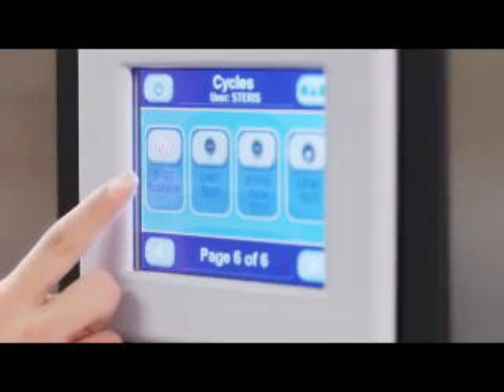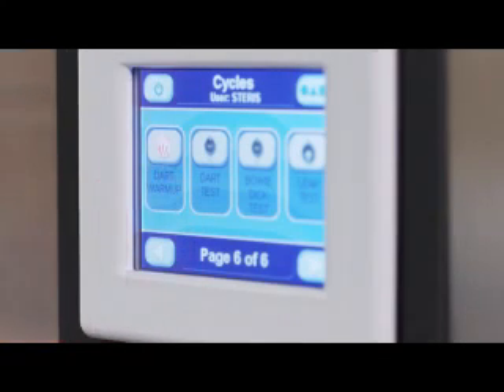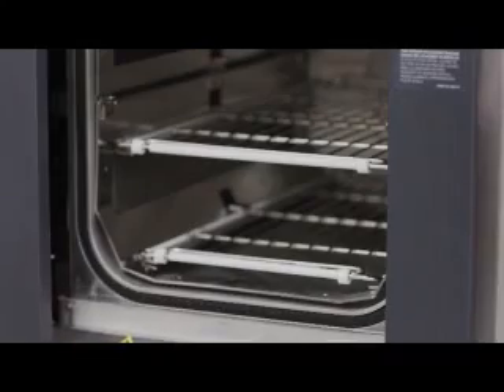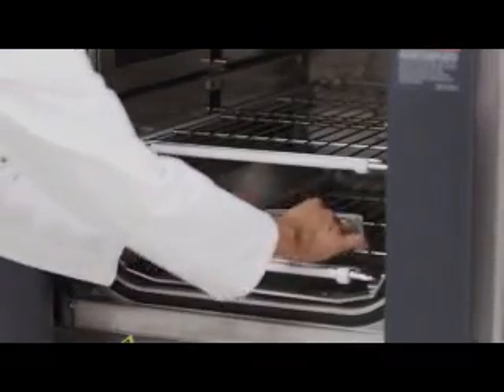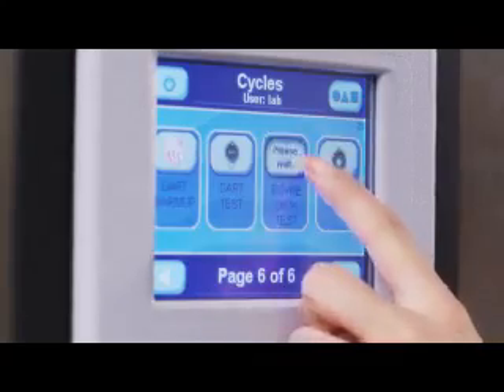Before running a DART or Bowie Dick test, you must first run a warm-up cycle. When ready, place the test pack on the bottom shelf above the chamber drain and close the door.